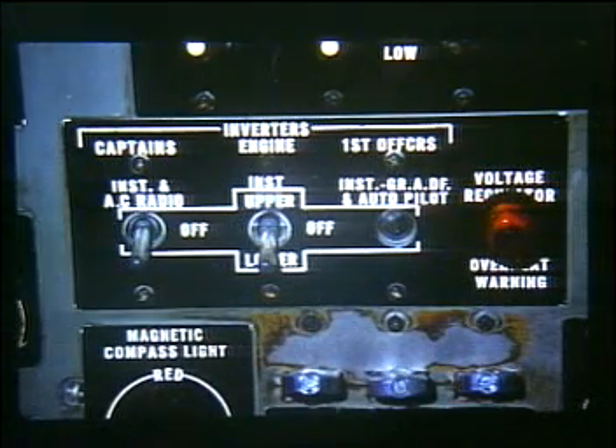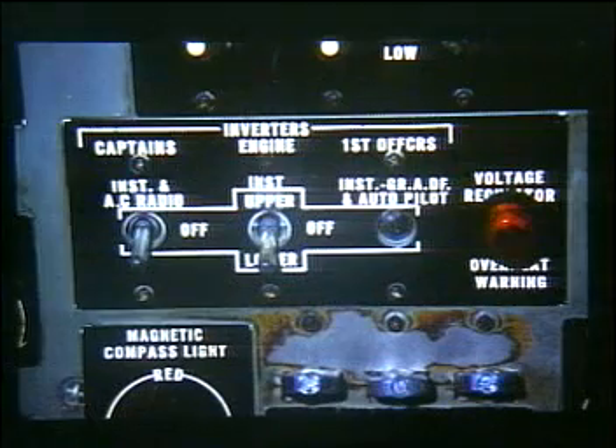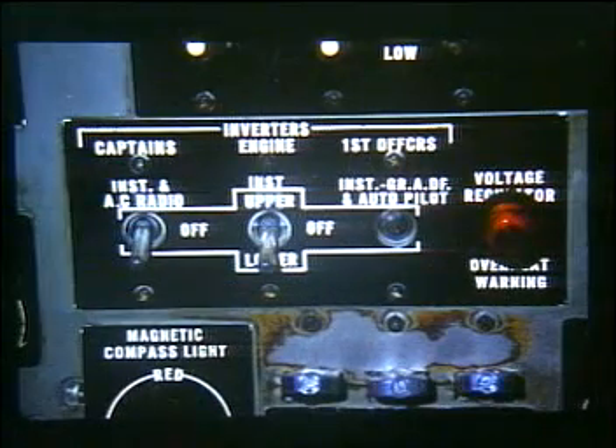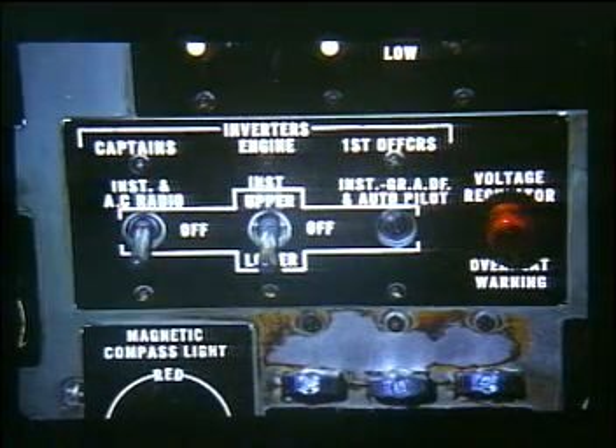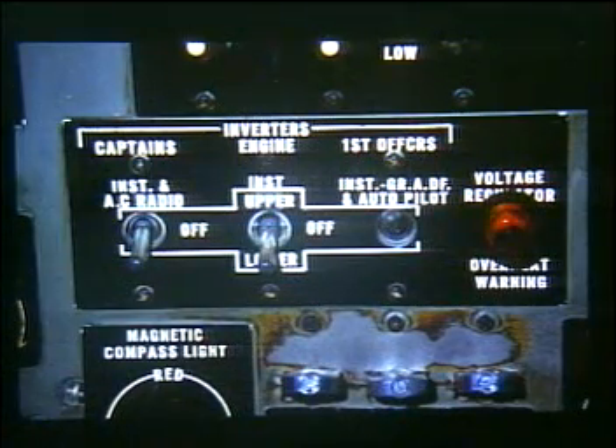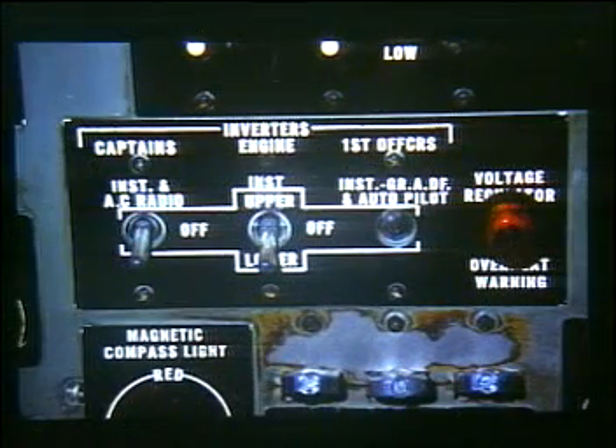3 switches in the cockpit, located on the center overhead instrument panel, provide control over the inverters. Each switch is a 3-position switch, with the center position being off. Any of the switches, when placed in either the upper or lower position, is capable of starting the selected inverter. The switches also distribute the output of the inverter to the AC-operated equipment in the aircraft. Simply stated, the inverter switches provide on-off control over the inverters and distribution of its AC output to the designated equipment in the aircraft.